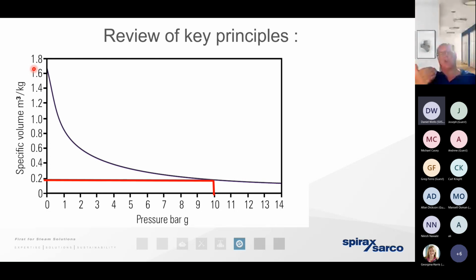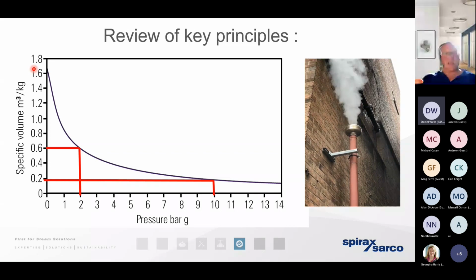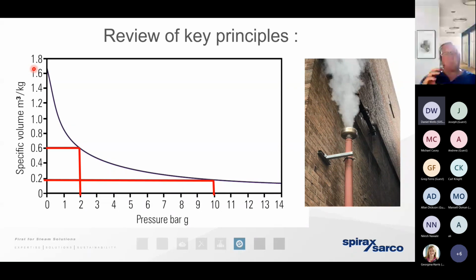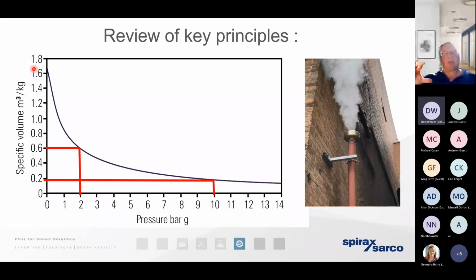Now, we've also mentioned that we need to have a pressure drop around the steam system. We've got to have a fall in pressure. So as that steam falls in pressure, whether it's across a pressure reducing valve, a control valve, or even across a steam trap that might have failed in the open position, what we're going to see is the fall in pressure brings around an expansion of that volume. So using the example of a steam trap that may have failed in the open position or an incorrectly sized pipework, we're at risk that we could have a significant expansion in that volume of steam. That's why we see flash steam vents located periodically around a steam and condensate loop. It's in order to protect the infrastructure from significant expansion that could do damage. So that explains the pressure volume relationship.